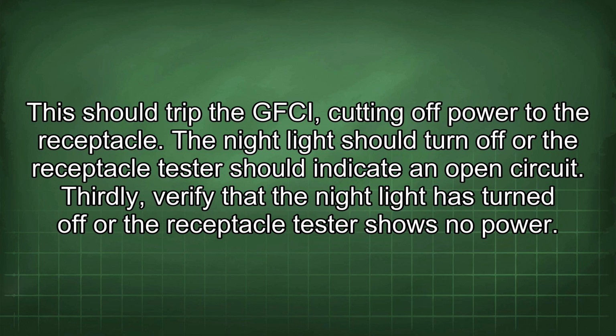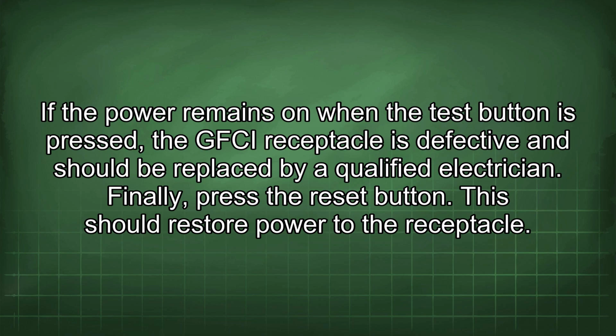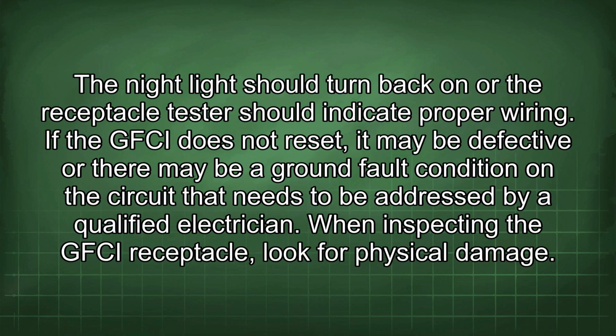Thirdly, verify that the night light has turned off or the receptacle tester shows no power. If the power remains on when the test button is pressed, the GFCI receptacle is defective and should be replaced by a qualified electrician. Finally, press the reset button. This should restore power to the receptacle. The night light should turn back on or the receptacle tester should indicate proper wiring. If the GFCI does not reset, it may be defective or there may be a ground fault condition in the circuit that needs to be addressed by a qualified electrician.